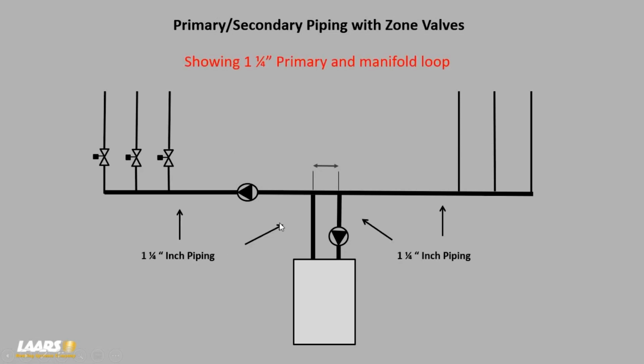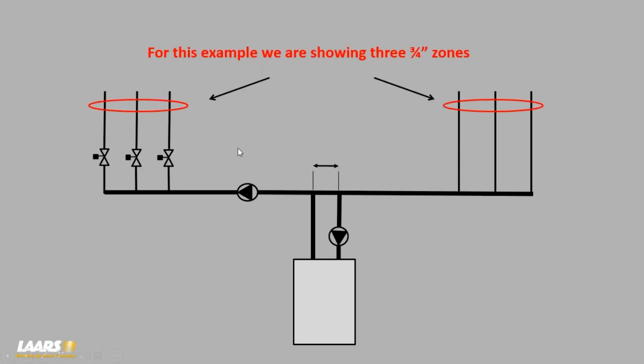Next, we're going to show 1.25-inch manifold. We're also showing here in this example 3 3/4-inch zones. Why? Because a lot of these jobs are being utilized for baseboard heat. Older systems had baseboard heat and 3/4-inch pipe, so that's what this example is.